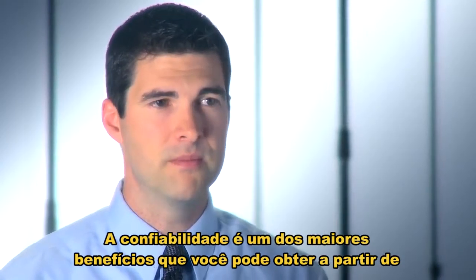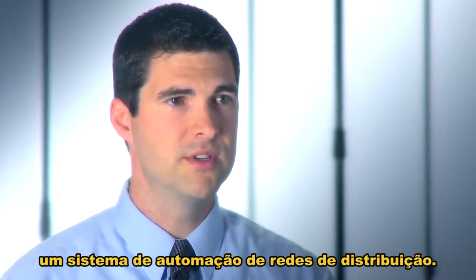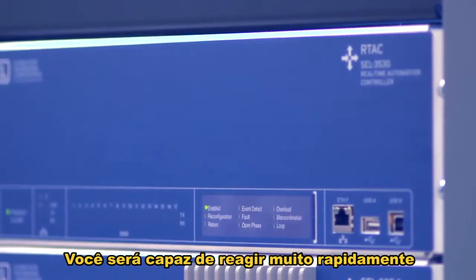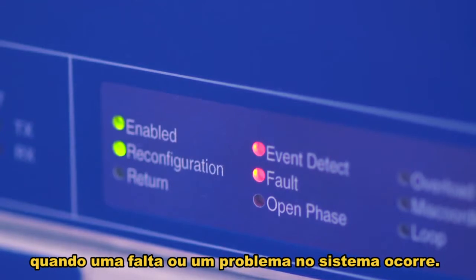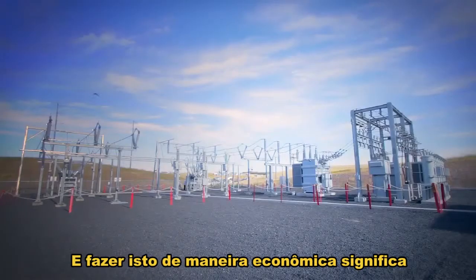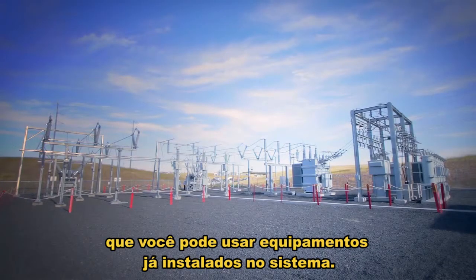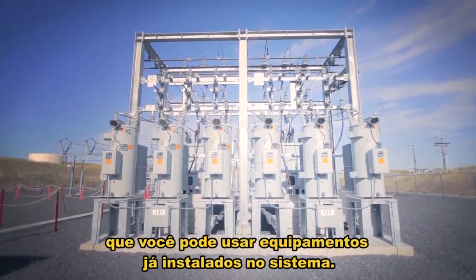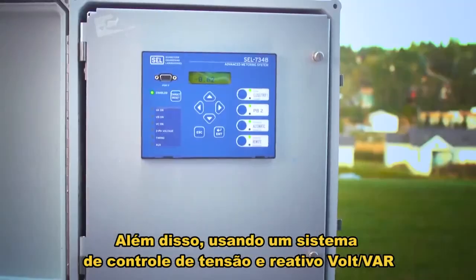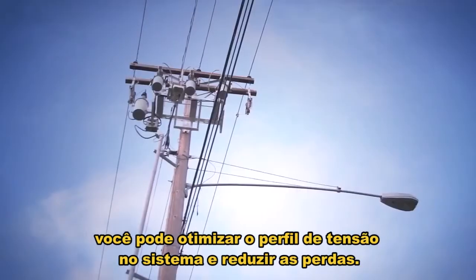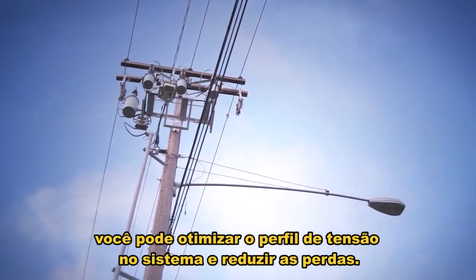Reliability is one of the biggest benefits you can get from a distribution automation system. You're going to be able to react very quickly when a fault happens or a problem happens in the system, and doing this economically means you can use the equipment that you already have on the system. Additionally, by using a volt VAR control system, you can optimize the voltage profile on the system and reduce losses.